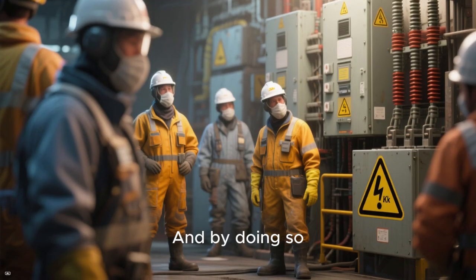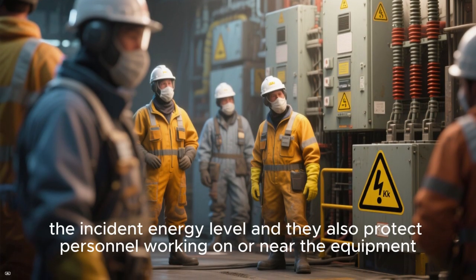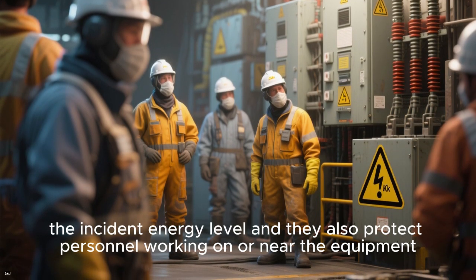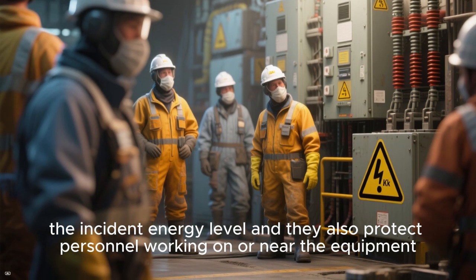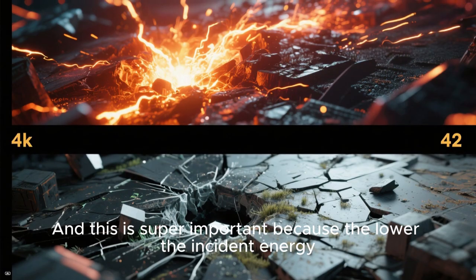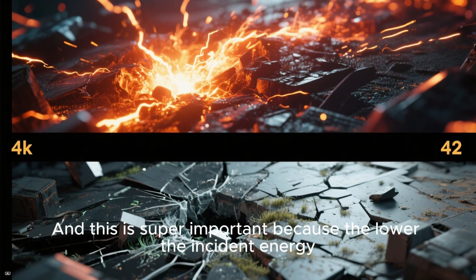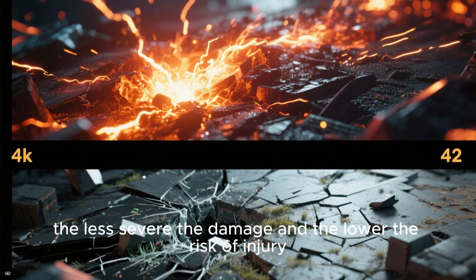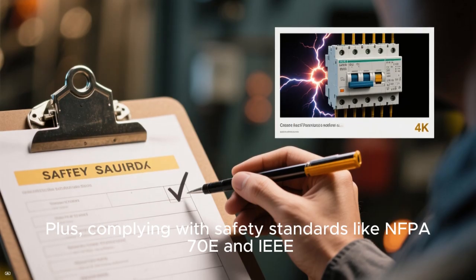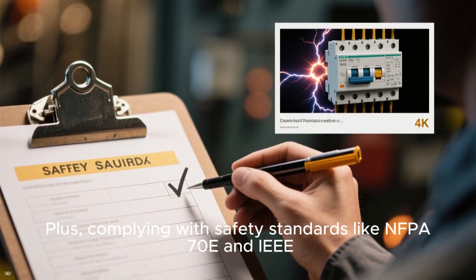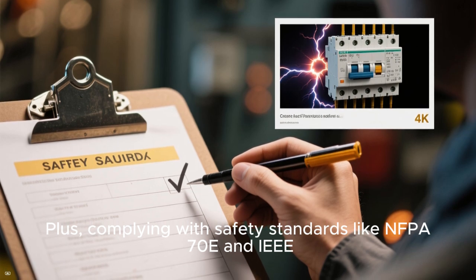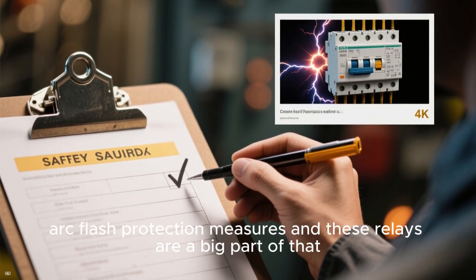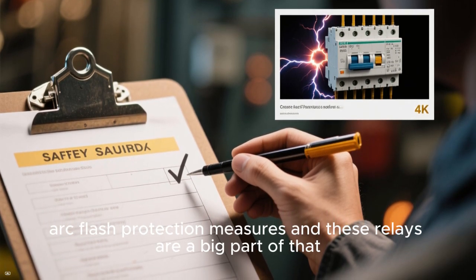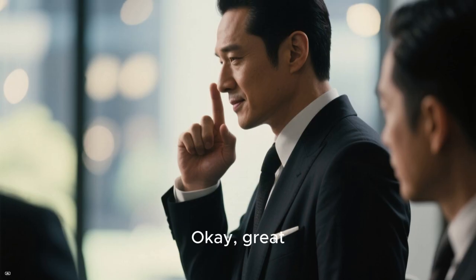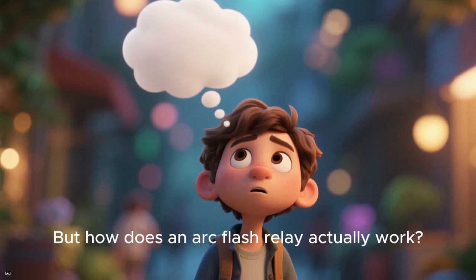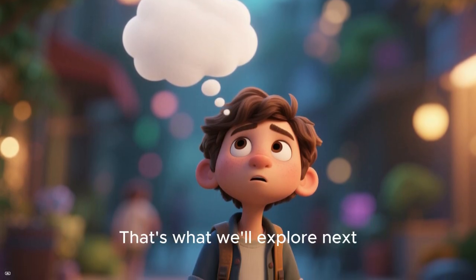And by doing so, these relays lower the incident energy level, and they also protect personnel working on or near the equipment. And this is super important because the lower the incident energy, the less severe the damage, and the lower the risk of injury. Plus, complying with safety standards like NFPA 70E and IEEE 1584 requires arc flash protection measures, and these relays are a big part of that. Okay, great. But how does an arc flash relay actually work? That's what we'll explore next.